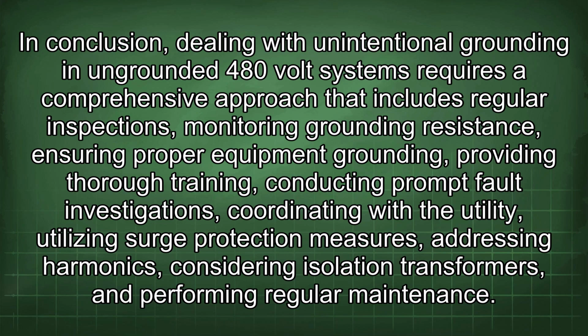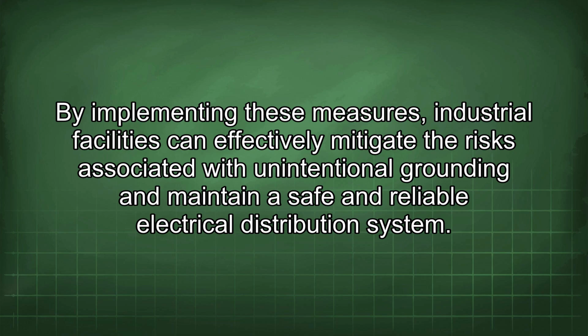In conclusion, dealing with unintentional grounding in ungrounded 480-volt systems requires a comprehensive approach that includes regular inspections, monitoring grounding resistance, ensuring proper equipment grounding, providing thorough training, conducting prompt fault investigations, coordinating with the utility, utilizing surge protection measures, addressing harmonics, considering isolation transformers, and performing regular maintenance. By implementing these measures, industrial facilities can effectively mitigate the risks associated with unintentional grounding and maintain a safe and reliable electrical distribution system.